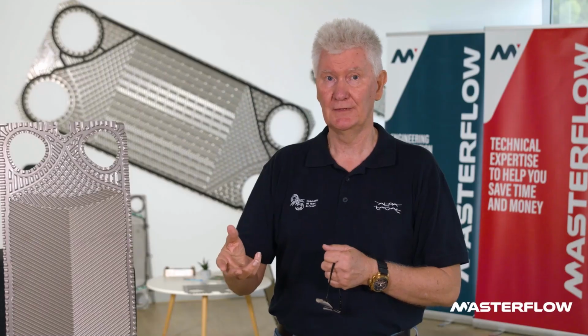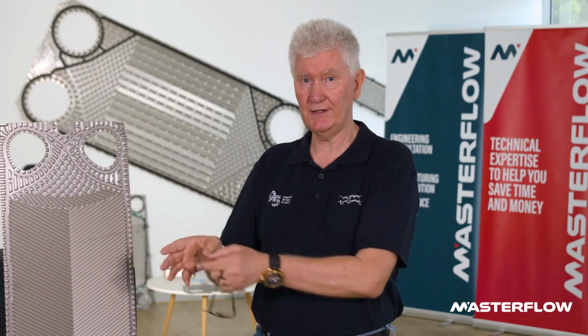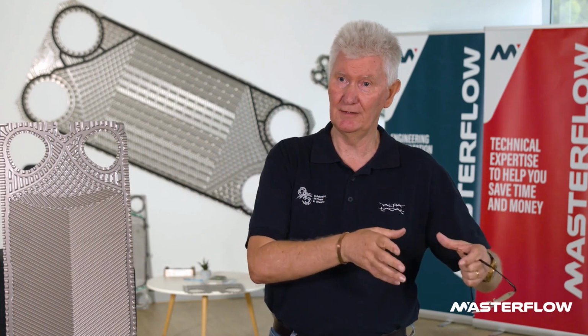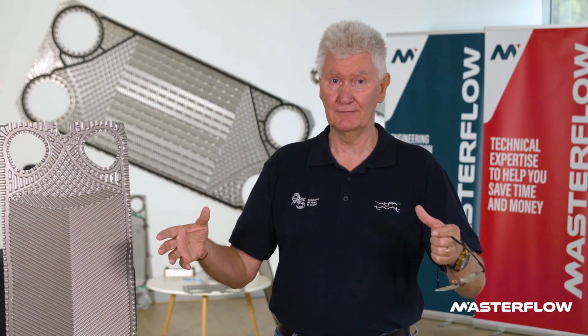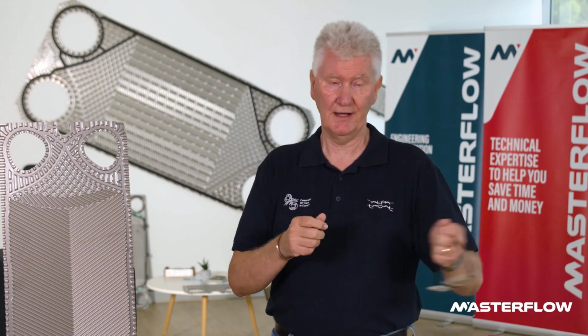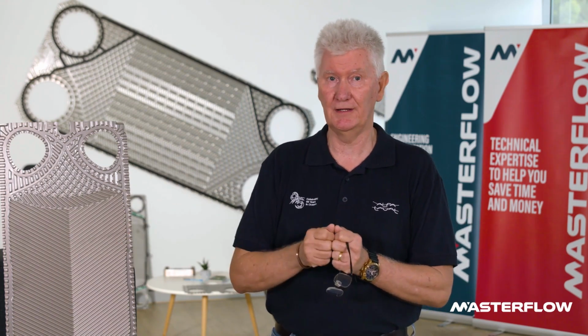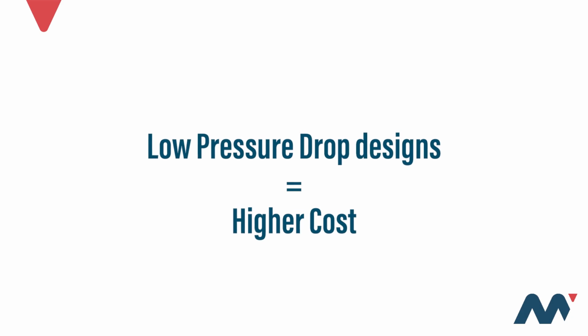Fouling is also related to wall shear. So fouling starts to increase with low velocities. So one has to look at how you design for winter and how you design for summer and come up with a compromise. Just saying one competitor has low pressure drop versus another competitor is not the right way of going. And don't forget, pressure drop is a sacrifice for heat transfer area. Low pressure drop designs cost you more to buy.